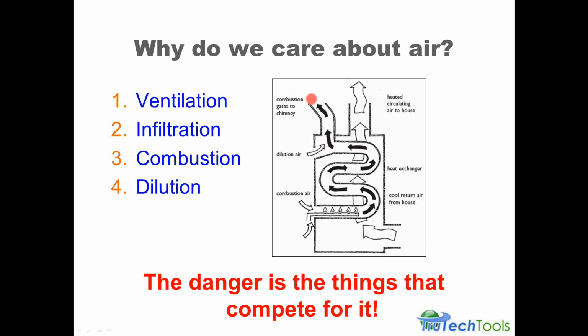the stack. So all four types of air here can come into competition, where if there is not enough infiltration air, perhaps after a building has been air tightened and air sealed, and we're relying upon that infiltration air to feed combustion and dilution. If that infiltration air is not available, it could deplete the way combustion is happening or the dilution air is happening.